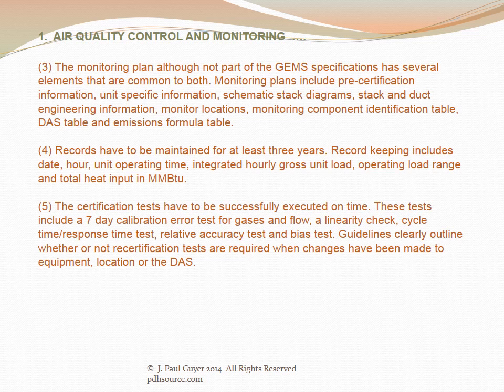Records have to be maintained for at least three years. Record keeping includes date, hour, unit operating time, integrated hourly gross unit load, operating load range, and total heat input in MMBTUs. The certification tests have to be successfully executed on time. These tests include a seven-day calibration error test for gases and flow, a linearity check, cycle time response time test, relative accuracy test, and bias test. Guidelines clearly outline whether or not recertification tests are required when changes have been made to equipment, location, or the DAS.